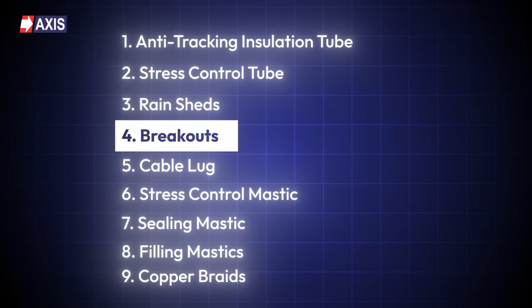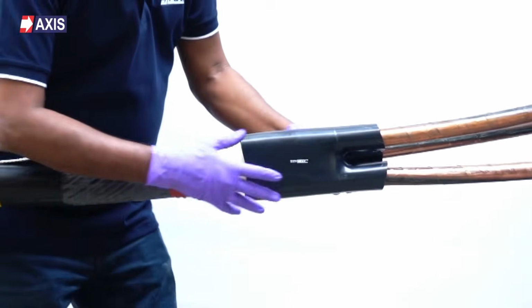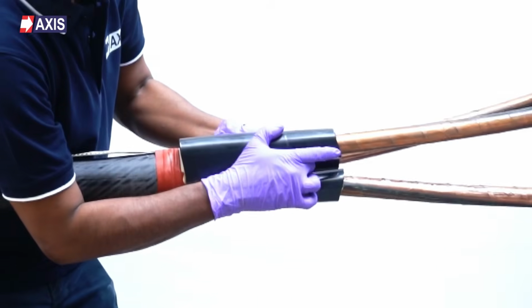Fourthly, breakouts. These are used to seal and insulate individual cores in multi-core cable terminations. They prevent moisture, dust, and contaminants from entering the cable at the core separation point. Breakouts are used in both indoor and outdoor terminations to maintain insulation integrity and ensure long-term reliability.